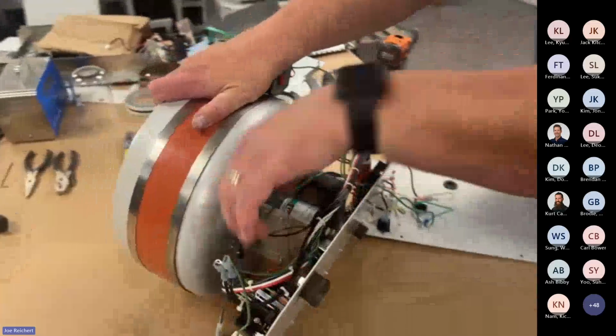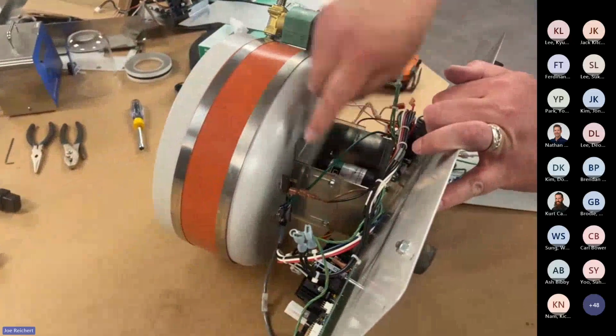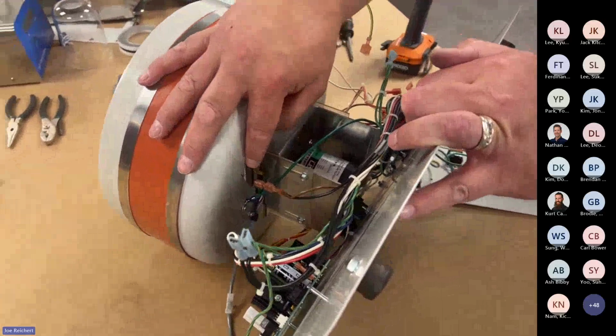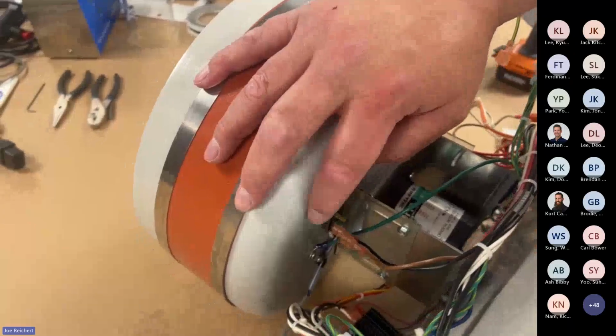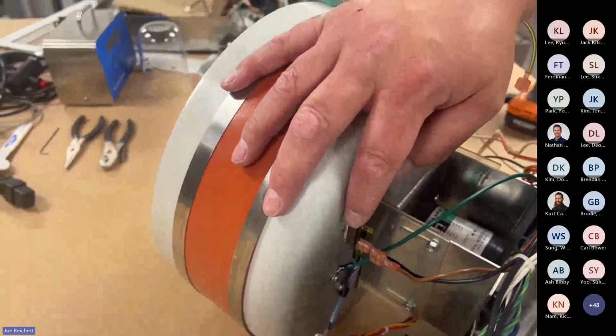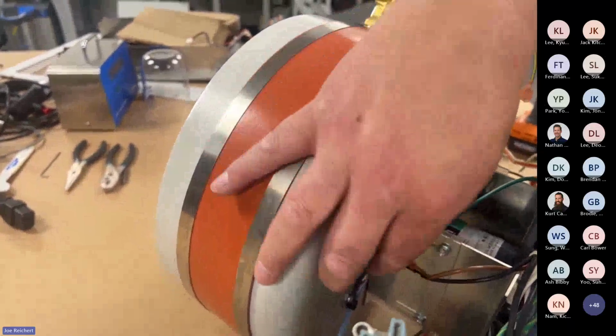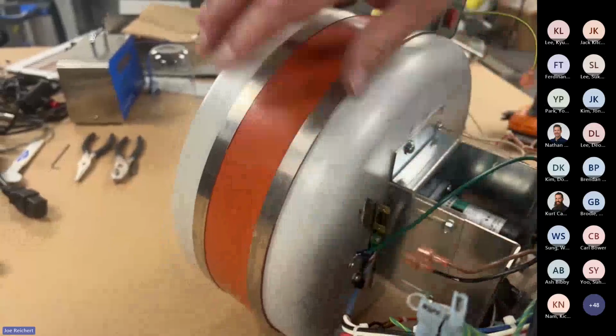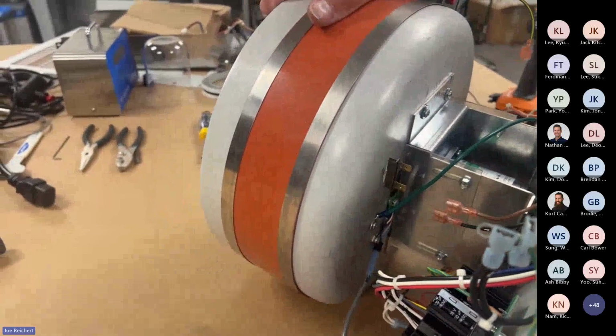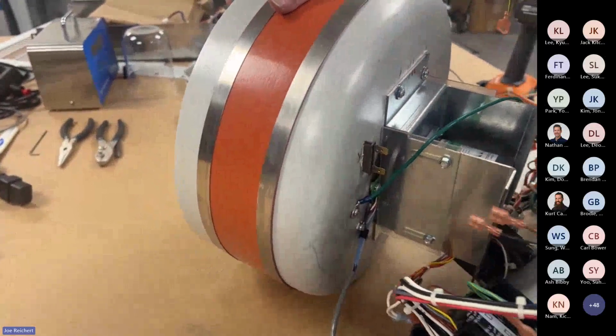Few more wires. This is a thermal overload protector. This was a single blow kind of thermal overload back then. If this popped, you had to replace it. Today's models have a thermal overload that is resettable, so once it cools off enough, it'll reset itself.